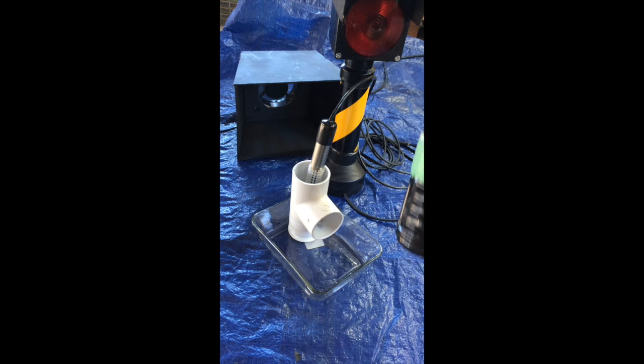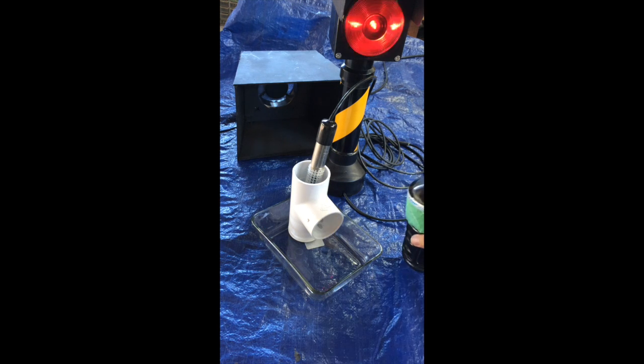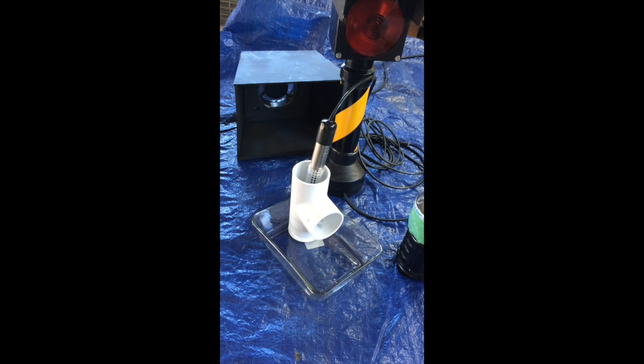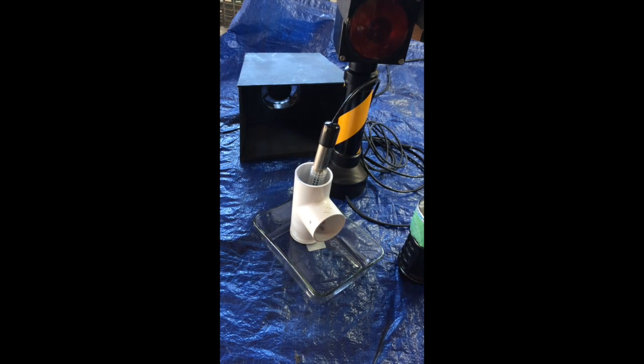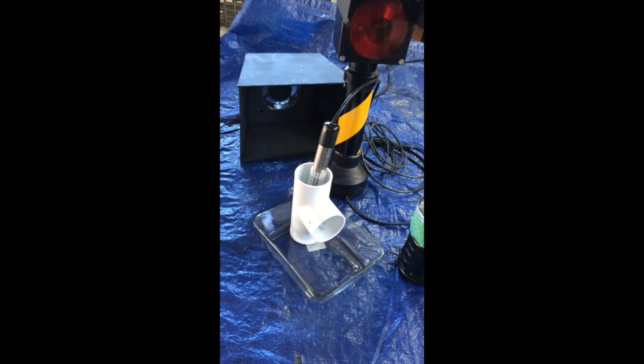We probably put in no more than about 30 or 40 milliliters, and the depth appears to be just about the bottom 2 centimeters or 3 centimeters of the probe. So we're going to stop the test here, put this foul-smelling brine back in its container, and then we'll proceed to do the test again with naphtha, and then lastly with water.